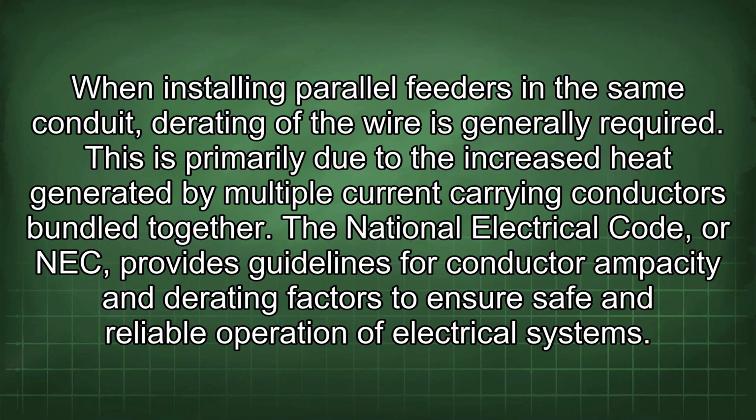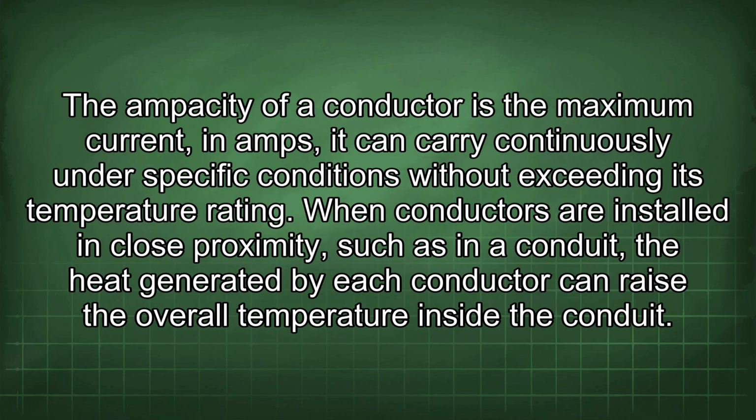When installing parallel feeders in the same conduit, derating of the wire is generally required. This is primarily due to the increased heat generated by multiple current-carrying conductors bundled together. The National Electrical Code, or NEC, provides guidelines for conductor ampacity and derating factors to ensure safe and reliable operation of electrical systems. The ampacity of a conductor is the maximum current, in amps, it can carry continuously under specific conditions without exceeding its temperature rating.